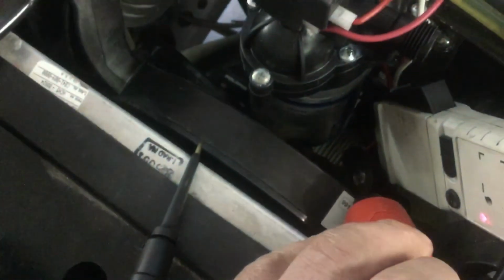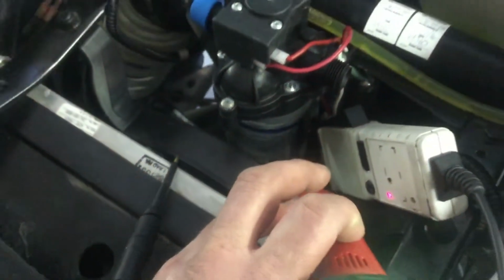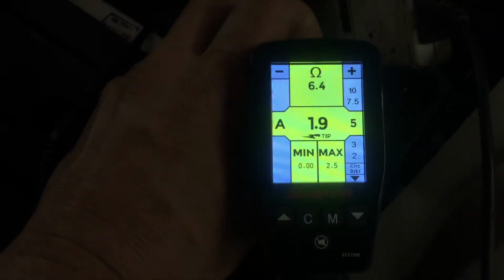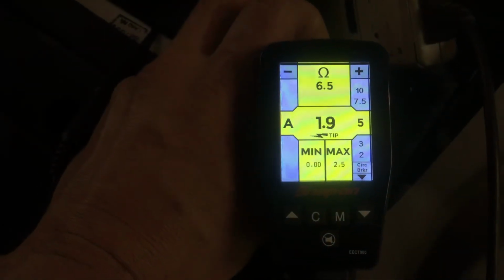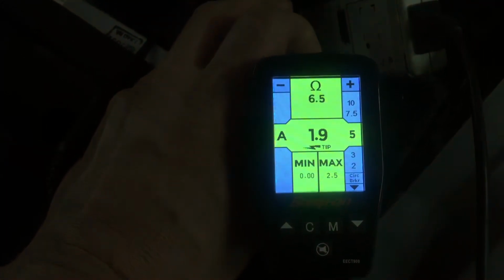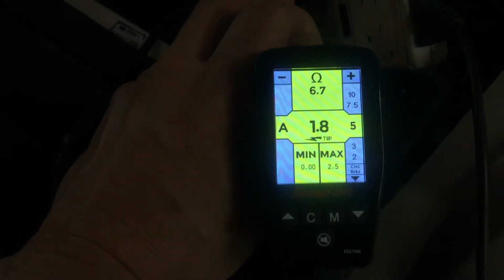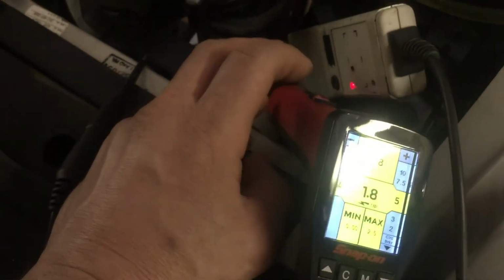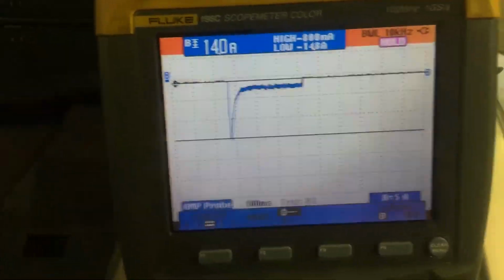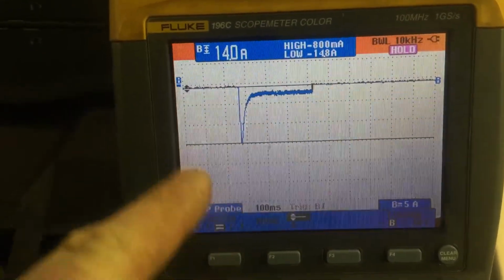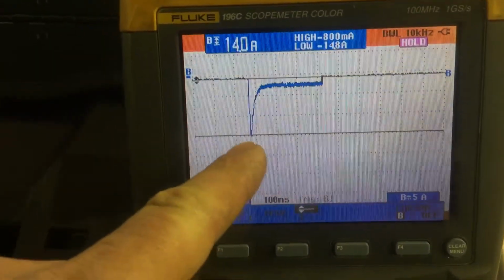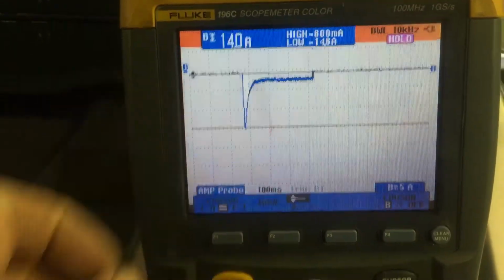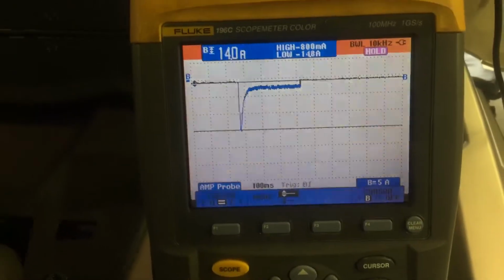I hit the button on the top. The pump's going. 6.4 ohms it says for resistance, and 1.9 amps at the tip. But I want to show you that when it first started up, it took 14 amps to get it to roll, and then up here, let's move the cursor up.